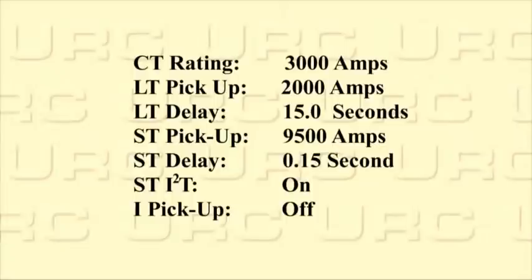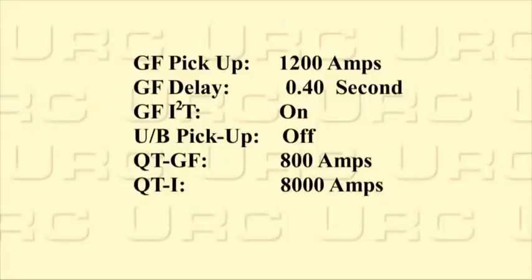Short time pickup 9500 amps, short time delay 0.15 seconds, short time I2T on, instantaneous pickup off, ground fault pickup 1200 amp, ground fault delay 0.40 seconds, ground fault I2T on, unbalanced pickup off, quick trip ground fault 800 amp, quick trip instantaneous 8,000 amps.